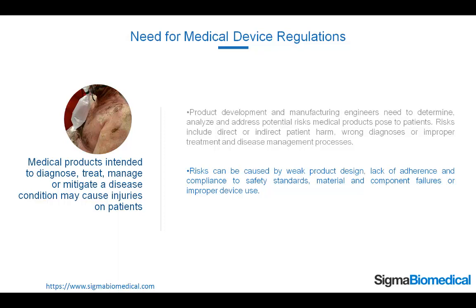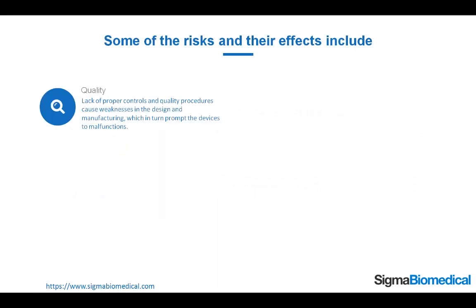Risks can be caused due to weak product design, lack of adherence and compliance to safety standards, material and component failures, or improper device use. Some of the risks and their effects include quality: lack of proper controls and quality procedures cause weaknesses in the design and manufacturing, which in turn prompt the devices to malfunction.